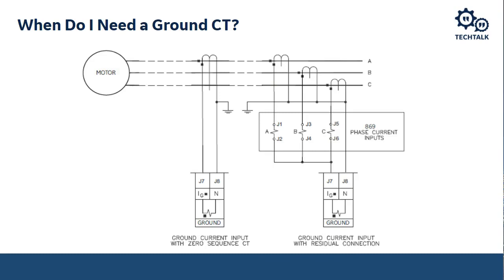So basically what we do is we have that ground CT, and all three phases of the conductors go through the hole in that CT. So the output of that CT is the addition of those three phases, and hence we get our ground current. In a normal condition, again, in a balanced condition, there's no ground fault current flowing. However, when we do have a ground fault, the CT is going to be sized so that it's accurate and measures very low ground fault current. The disadvantage of using this is that, depending on the size of the conductors, we will have to have a large enough hole in the CT for those conductors to fit through.